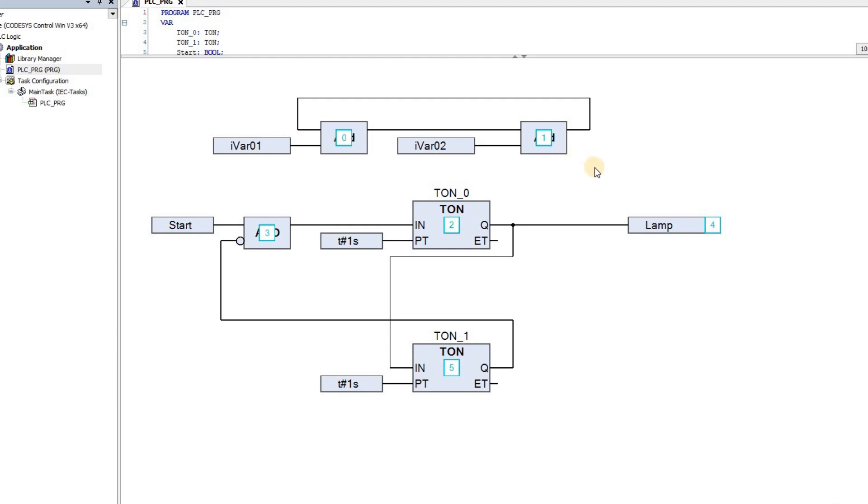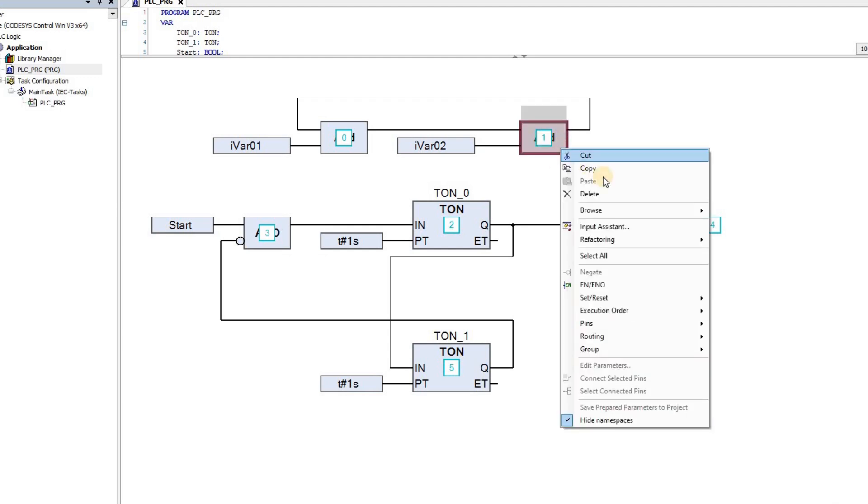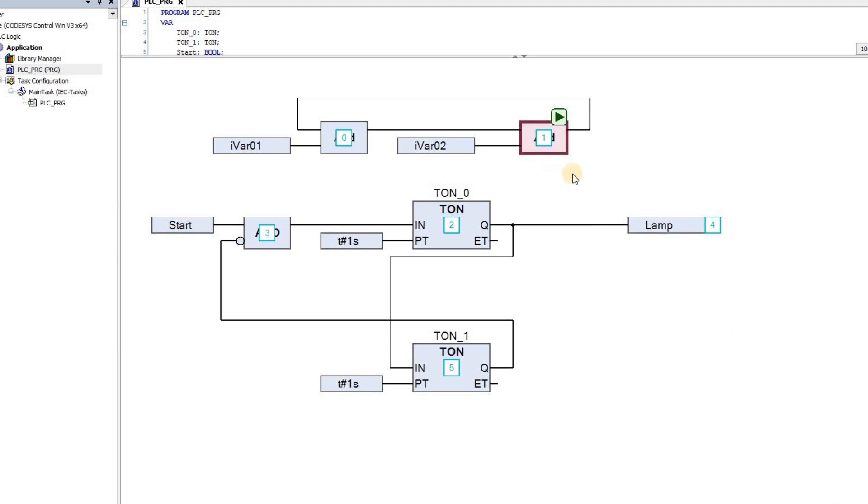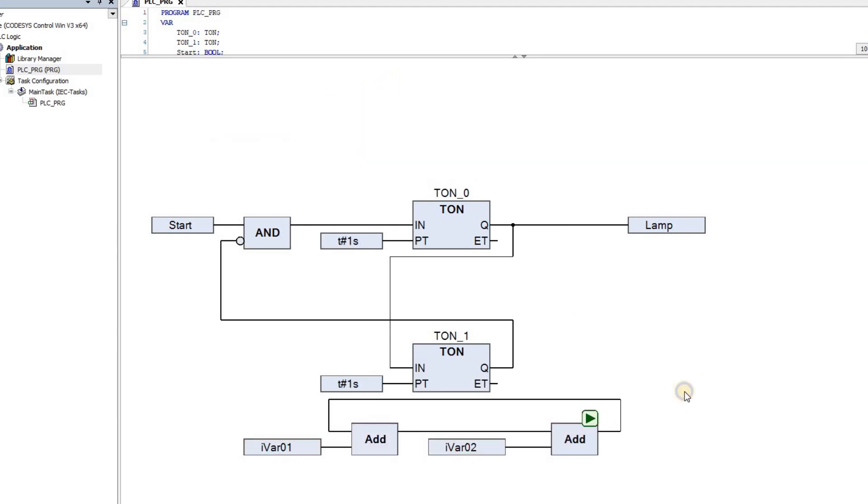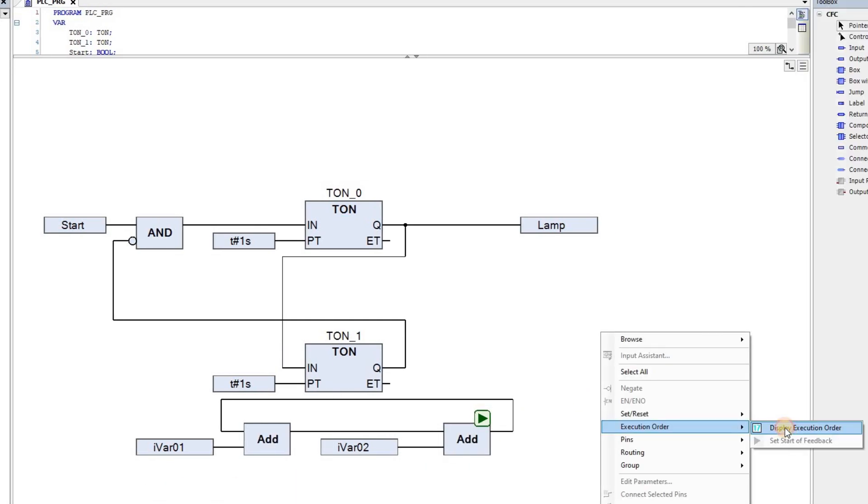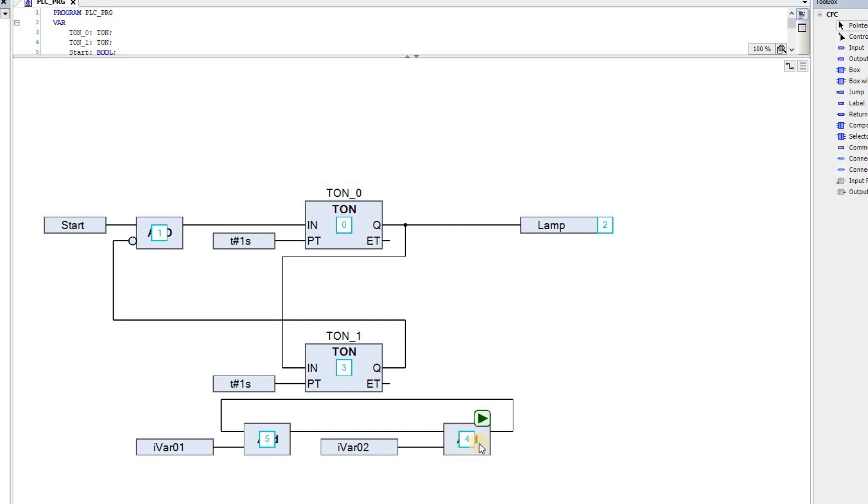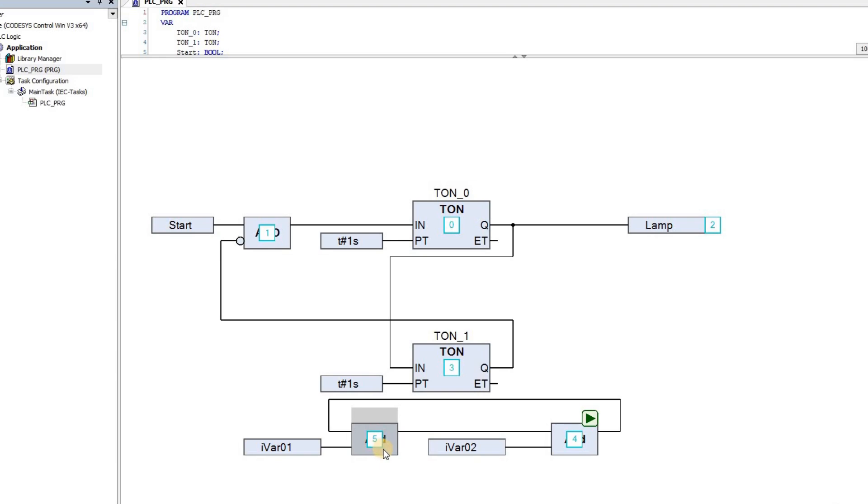Another point to check here is important for the networks including the feedback pass. In this case, if you right-click on a block, in the Execution order menu, there is this option to set Start of Feedback. If I choose it, a green small square will be shown in the corner of the block, and it determines that this block will be executed first, and its output will be used by the other blocks in the network. To update the execution order, I will move this network once downwards. And if I show the display execution order, you will see that this block will be executed first, and then the other block in the network will be executed afterwards.